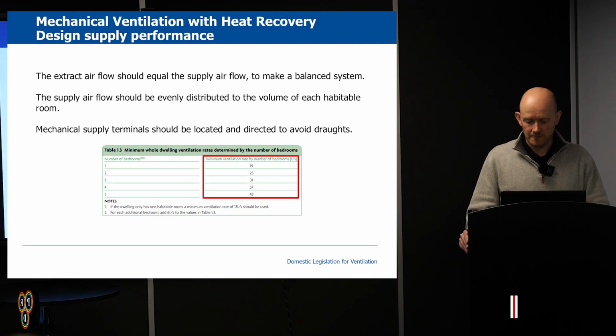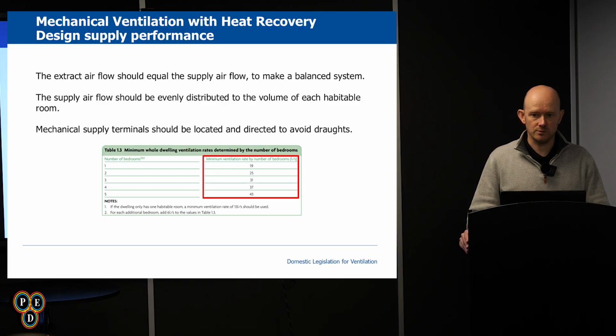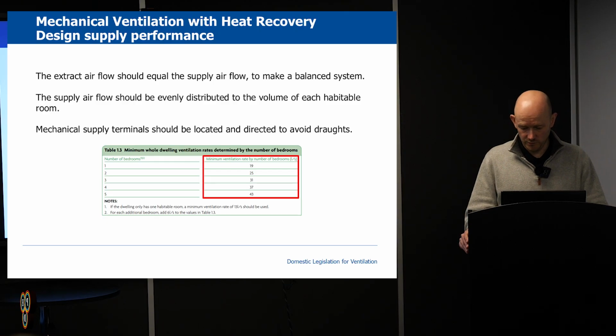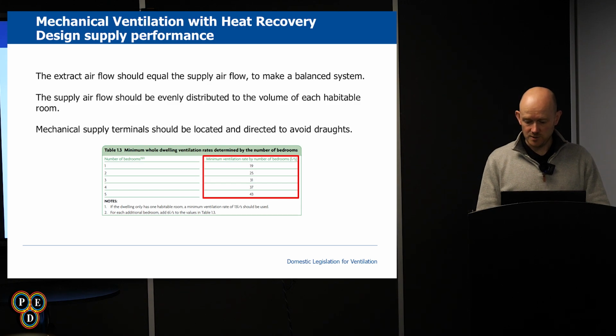Please note, background ventilators should not be installed with mechanical ventilation with heat recovery, as they provide unwanted additional ventilation and reduce the system's efficiency. So that's quite a common question: do I need trickle vents with this system? No, you don't need them at all. MVHR should be designed to avoid the moist air from the wet rooms recirculating to the habitable rooms.